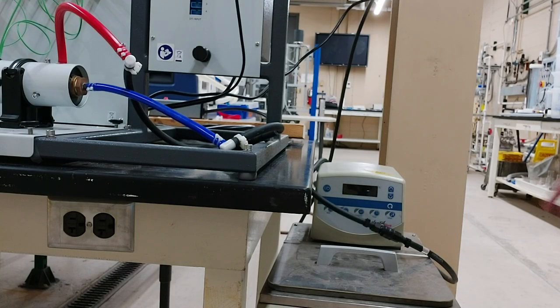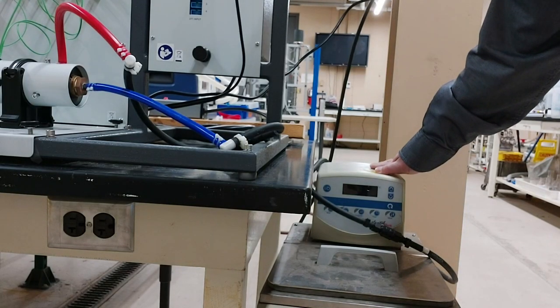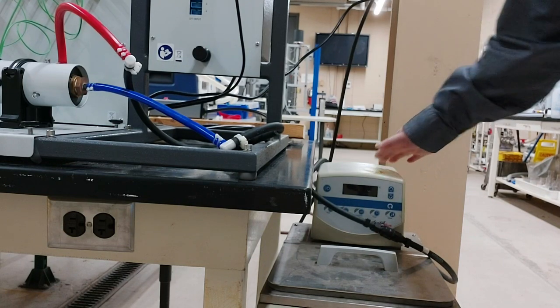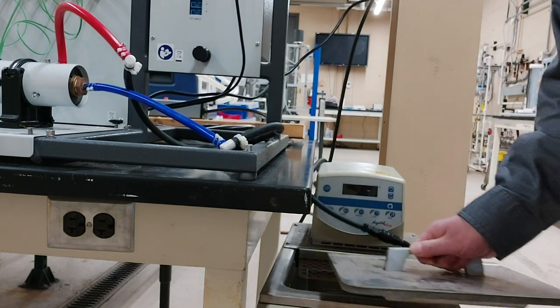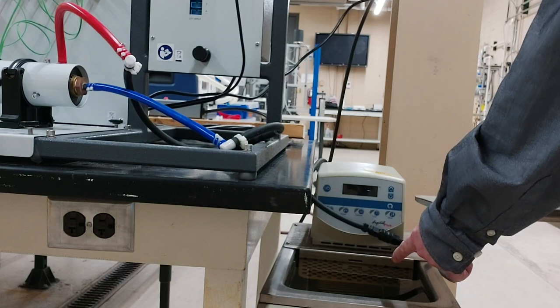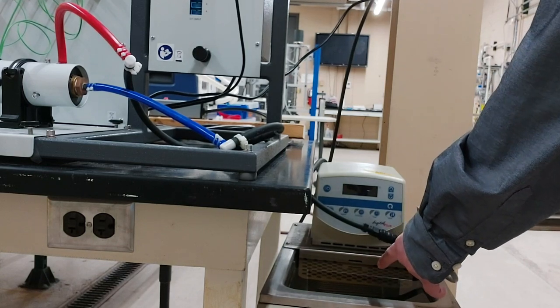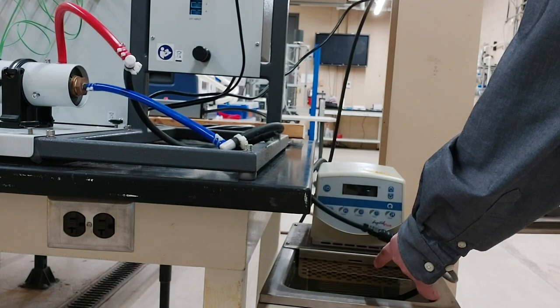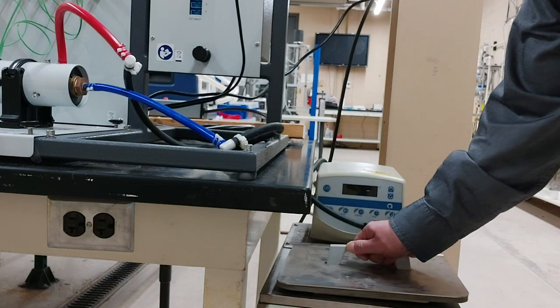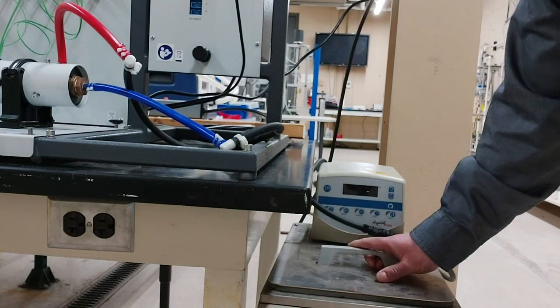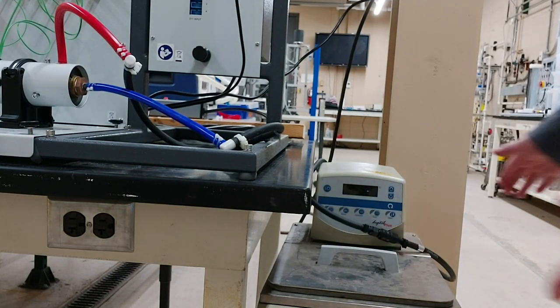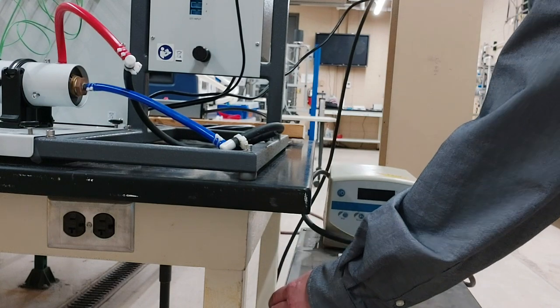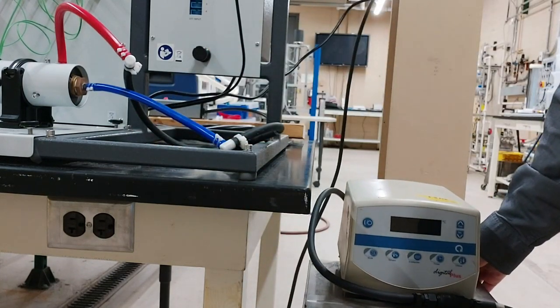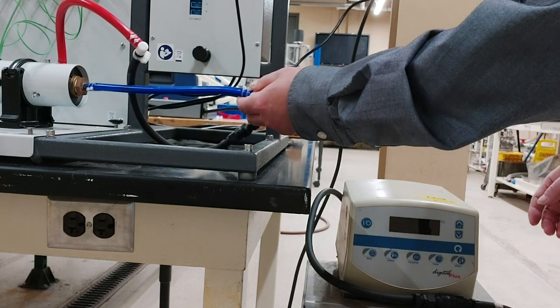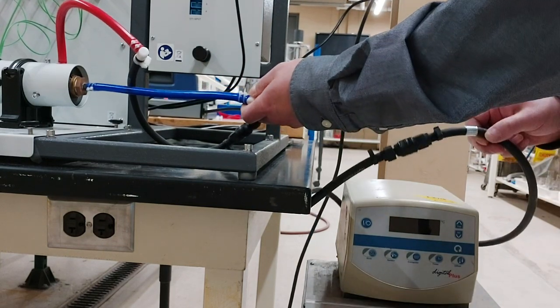Next, I will show you how to use this recirculating chiller. First, I want you to open this lid and make sure there is enough water inside. The water level should be within 1 inch from the top of the tub. If not, add more water. Then close the lid. Move the water chiller forward a little bit so the water tubes are closer to the water tubes from the instrument sample cylinder.